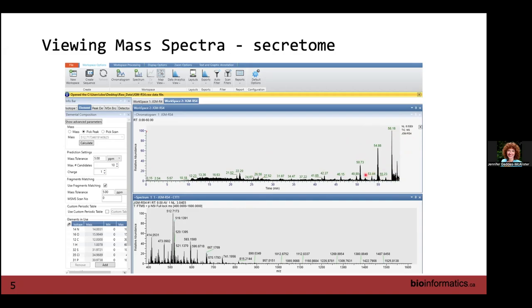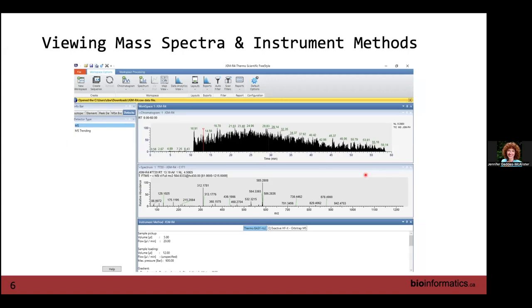Some high-abundant features appear at the end of the secretome chromatogram, masking the rest since it's all relative abundance. The repeating pattern of those peaks suggests a chemical contaminant — not necessarily a bad one. It could be polyethylene glycol, SDS, DTT, IAA, or other sample prep components that wash out at the end. Scrolling through the available windows in Freestyle shows the full chromatogram, gradient parameters, intensities, and solvent concentrations — all information you'd need for publication or method comparison.